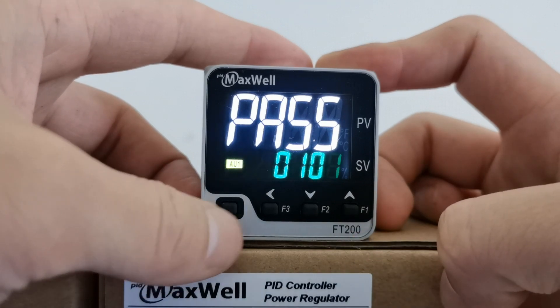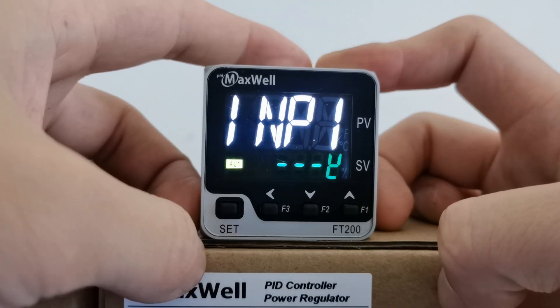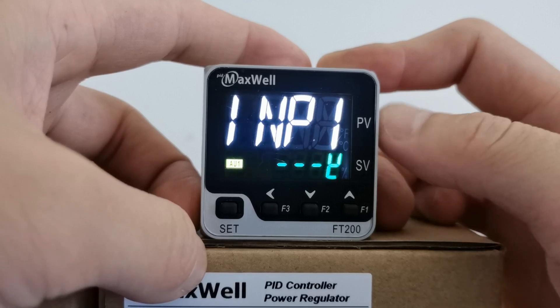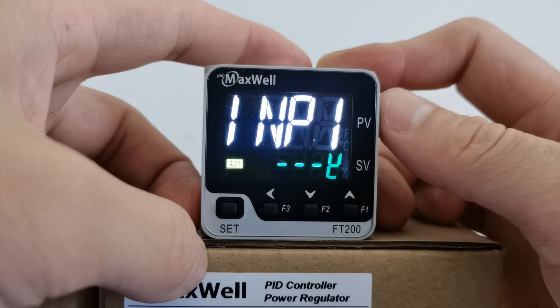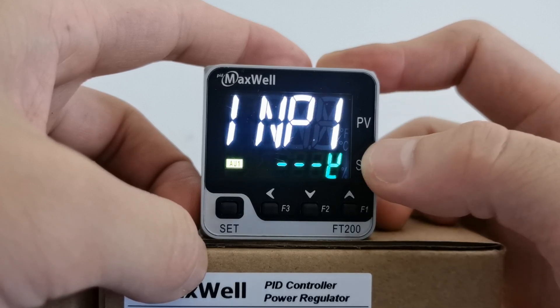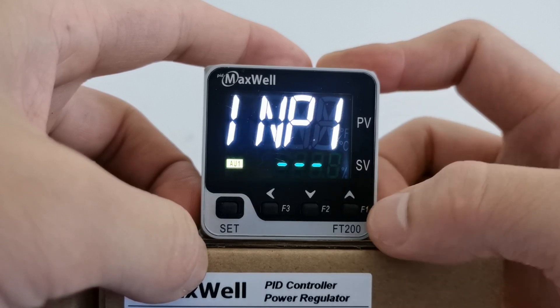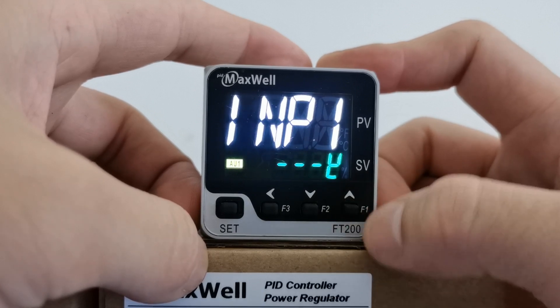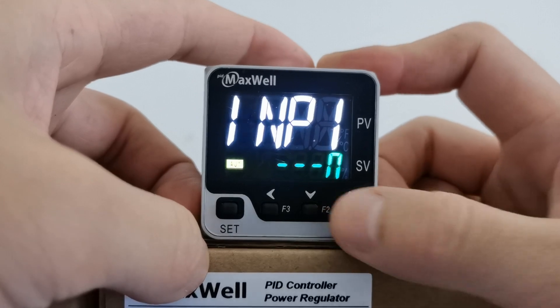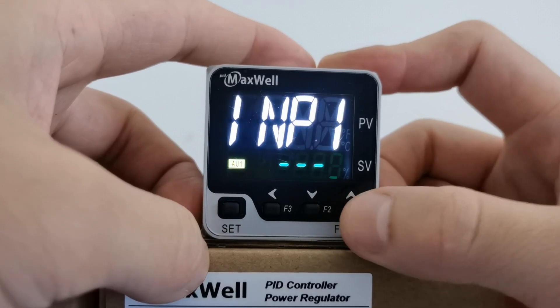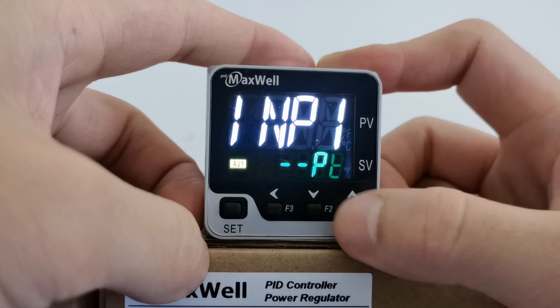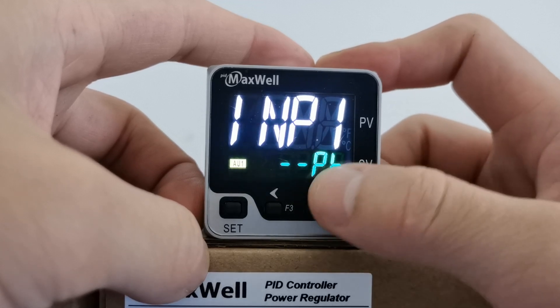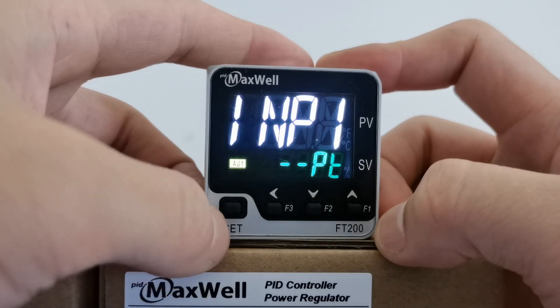Tap on the set button. The first parameter that pops up is where you can configure the input sensors. The factory default is type K thermocouple. For example, if you want to change that to PT100, just press the up button and there you go — you can see PT stands for PT100.